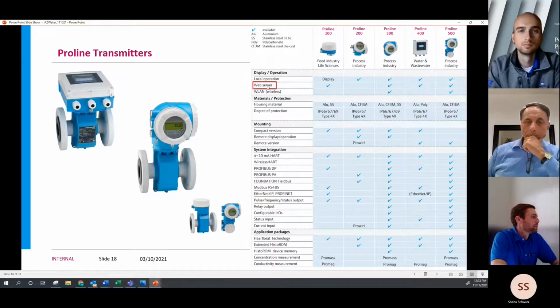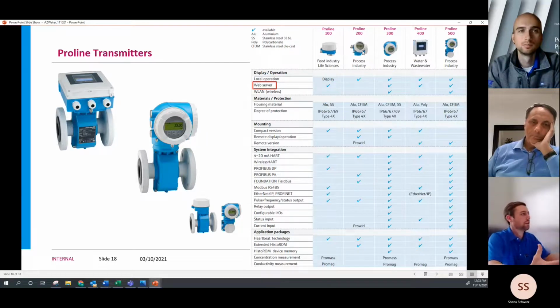There's a web server available on everything but the 2-wire device. So when configuring instruments, it's much easier to pull up a web server and connect into the instrument using your laptop, rather than pointing around on the transmitter itself.